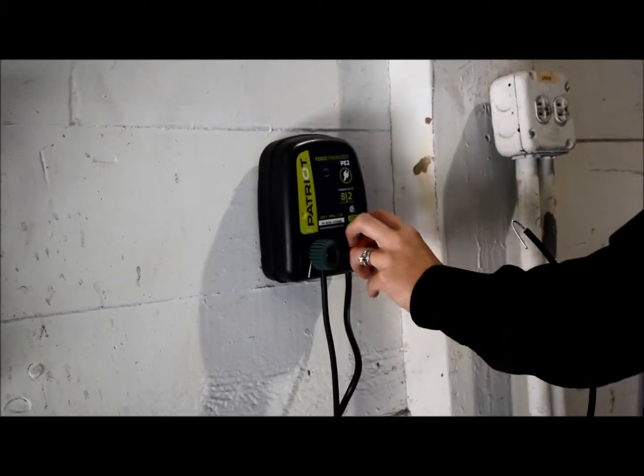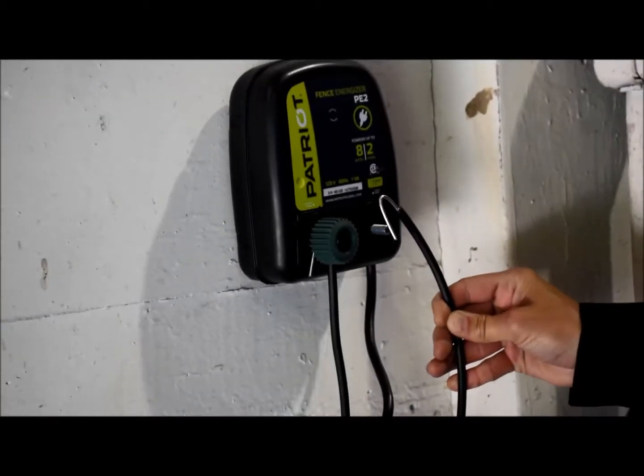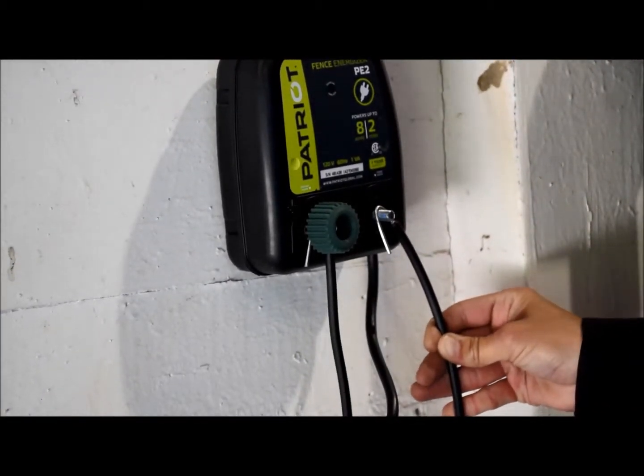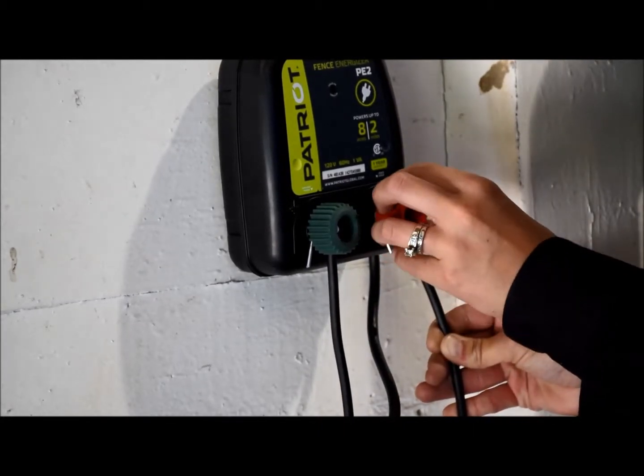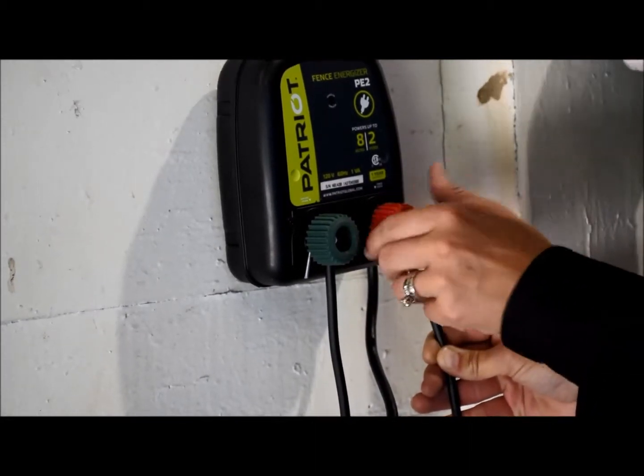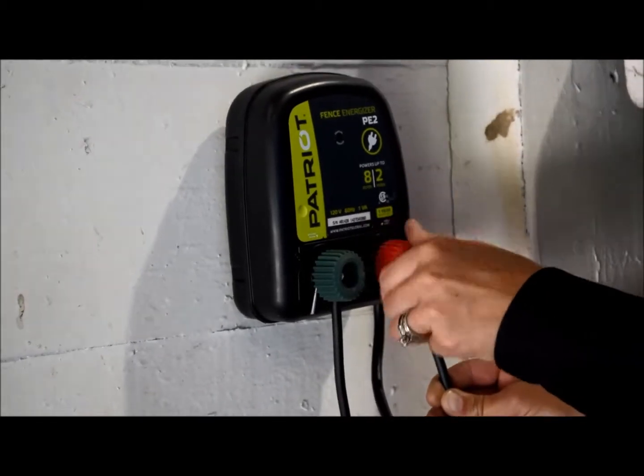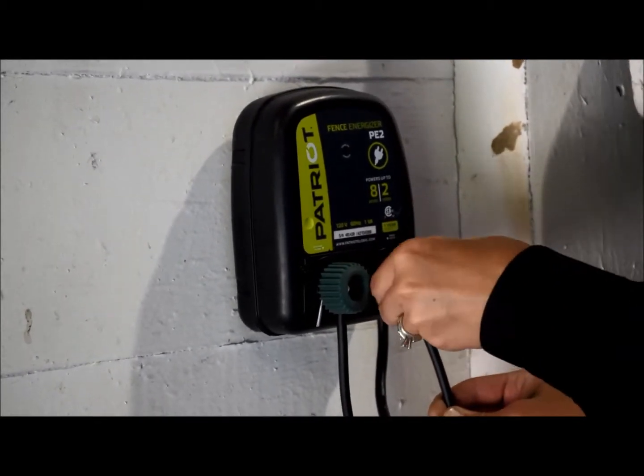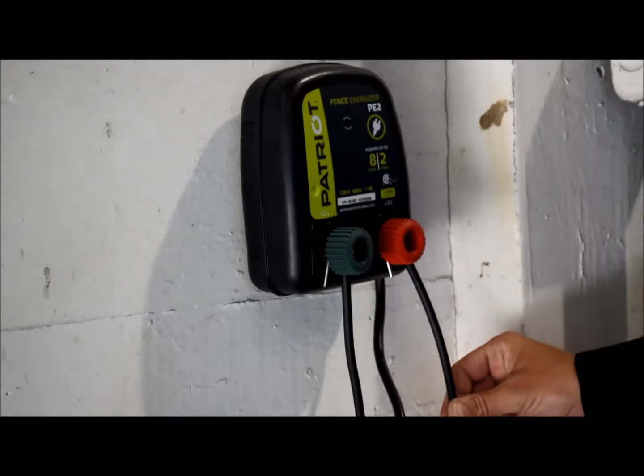Locate the end of the remaining underground cable. Strip away about 2 inches of coating and then make a small hook on the tip of the wire, similar to what you previously did. Loosen the red knob on the Energizer and place the hooked end of the underground cable over the metal terminal.